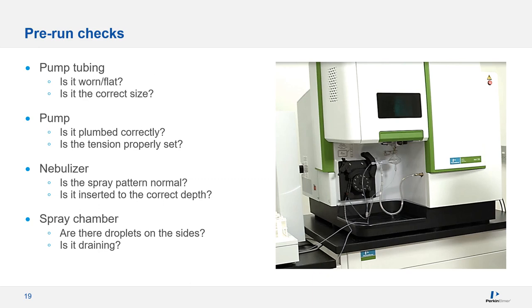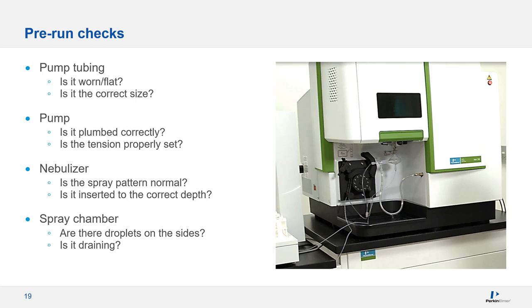Before you start a run, you'll want to verify that your sample introduction components are in good condition and installed properly. A quick checklist can be seen on this slide. Always be on the lookout for bubbles in the sample line that could indicate a loose connection between components. This is particularly true if you're using an internal standard mixing tee. Sometimes those, what look like bubbles, are actually voids in the line and can be caused by a kink in some piece of tubing or a partial plug beginning to form. So, it's not always a leak.